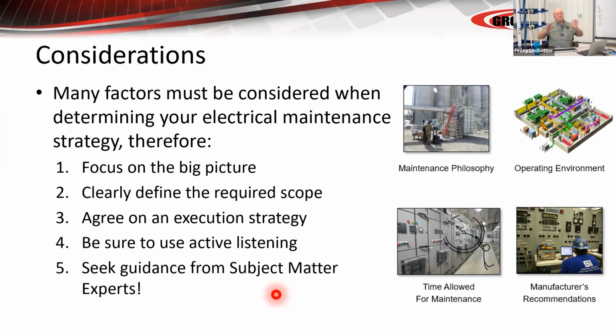But you know, your maintenance philosophy is, here's the big picture. We want to get all this equipment done. Here's the number of years we have to do it in, break it up in adequate segments, clearly define the individual scopes, agree on a strategy, agree on a contractor, be sure to use active listening. Listen to your contractor, listen to the users, interview people that are actually operating the equipment, and seek guidance from subject matter experts on things like circuit breakers, relaying, cable testing, PD testing. Find the people in the industry that really know.